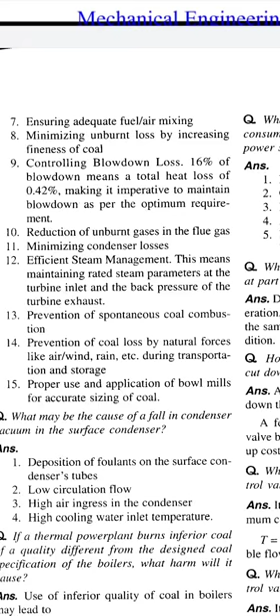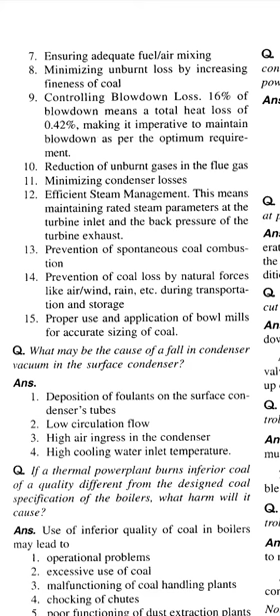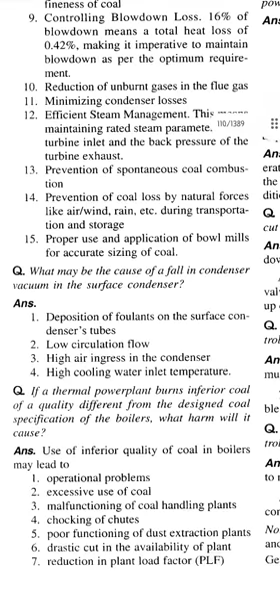Question. What may be the cause of a fall in condenser vacuum in the surface condenser? Answer. Deposition of fouling on the surface condenser tubes, low circulation water flow, high air ingress in the condenser, high cooling water inlet temperature.